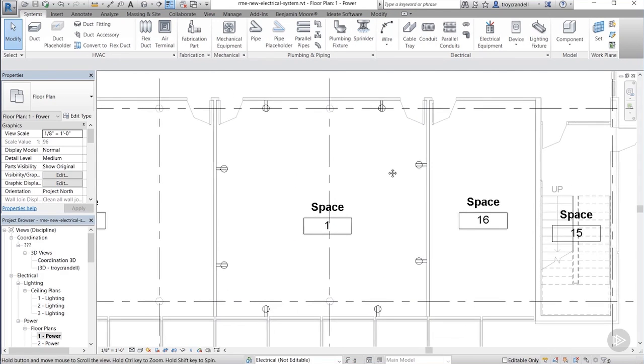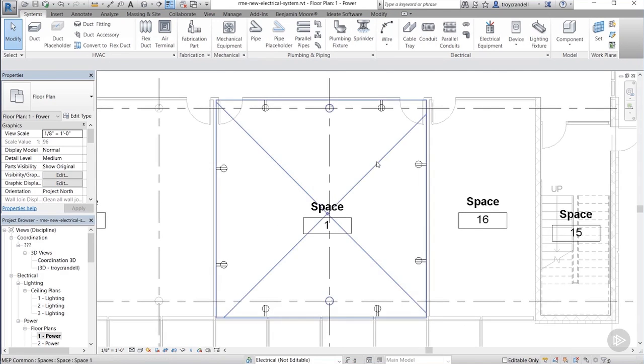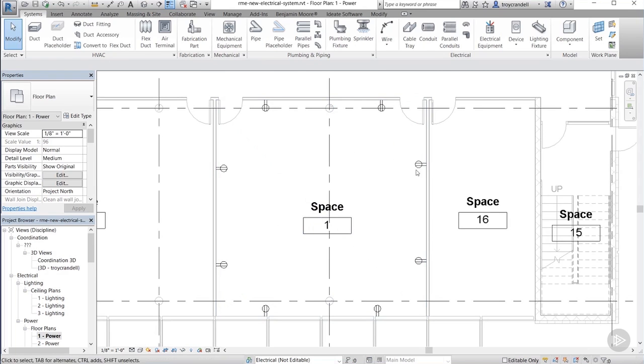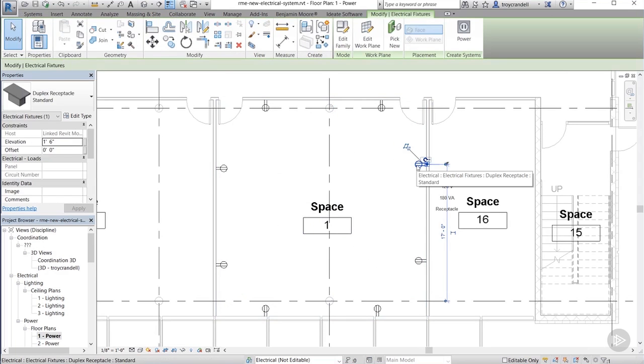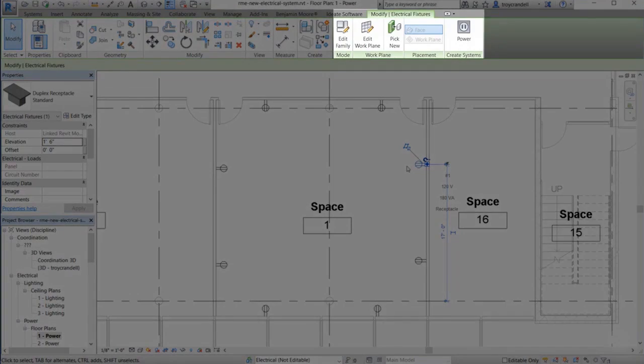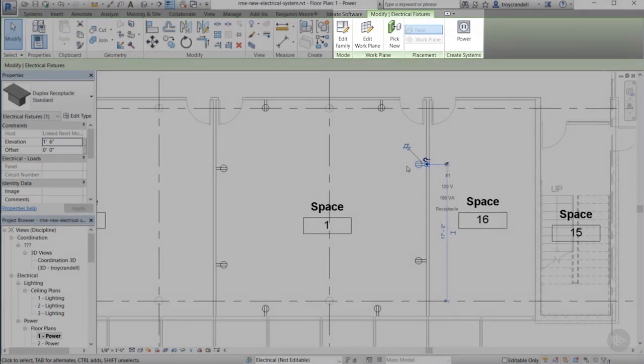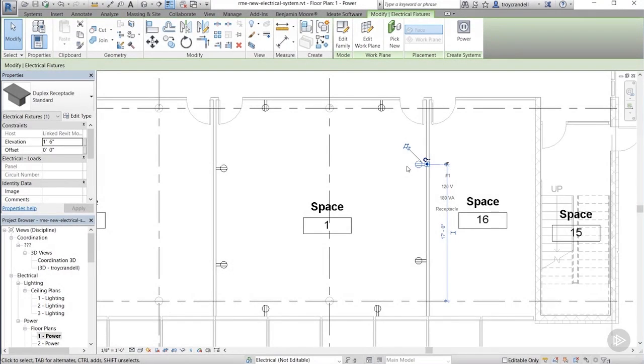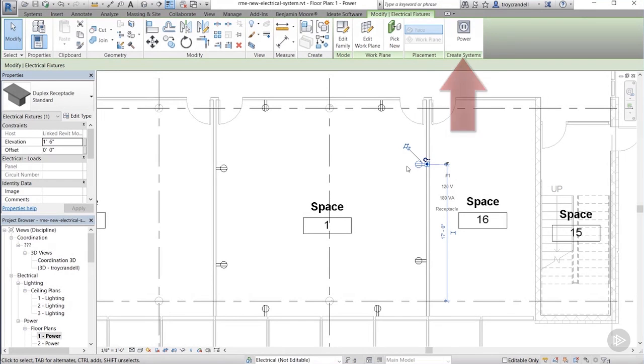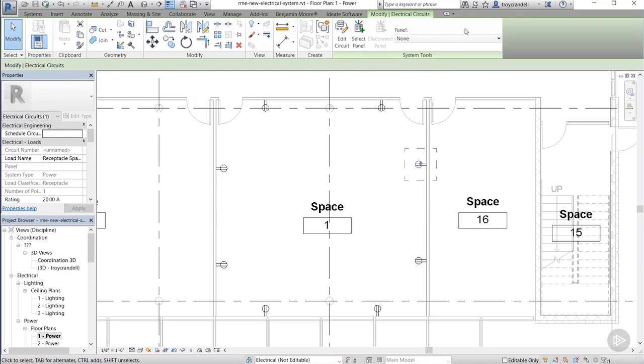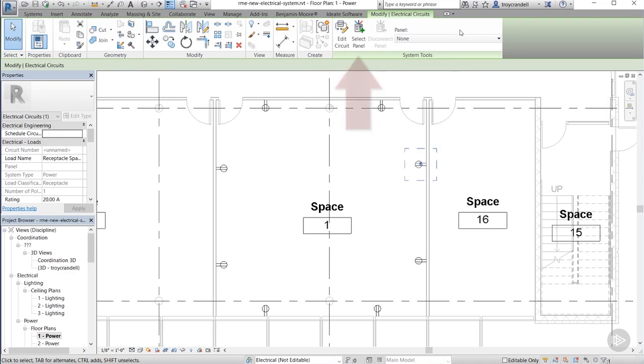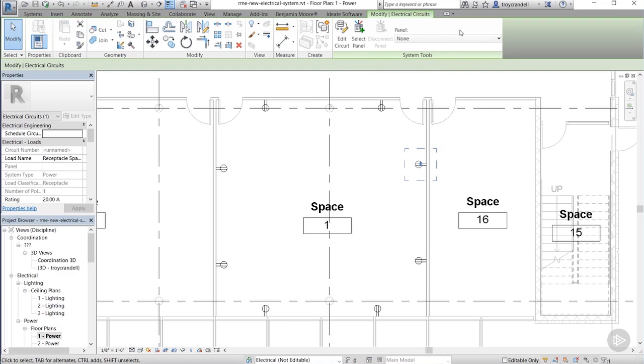Now, here's where it gets fun. Go ahead and select one of the receptacles. It doesn't actually matter which one you select. Once you select it, you'll notice on the ribbon, the contextual tools will be active. On the far right side, you'll see the create systems panel and the power button on that panel. Go ahead and click that. Now, that will bring up a set of new contextual tools. On the system tools panel, we have edit circuit, select panel, and then panel up above a little dropdown bar that has none in it at the moment. Now, since we have started to create our power system, we're going to want to edit this particular circuit. So, go ahead and click the edit circuit button.